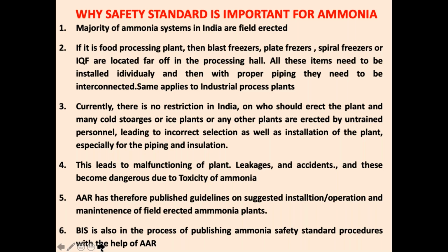And accidents are dangerous due to the toxicity of ammonia. Ammonia, as we discussed in our second session, is toxic and a little bit above a particular percentage it is flammable. But we also discussed that flammability is not an issue because the ignition temperature is very high, 650 degrees centigrade. So toxicity and leakage of ammonia is the main issue. And we are going to discuss today how to build a plant which will not leak. When you go to the machine room or plant room, you should be wondering whether this plant has ammonia or some other refrigerant.